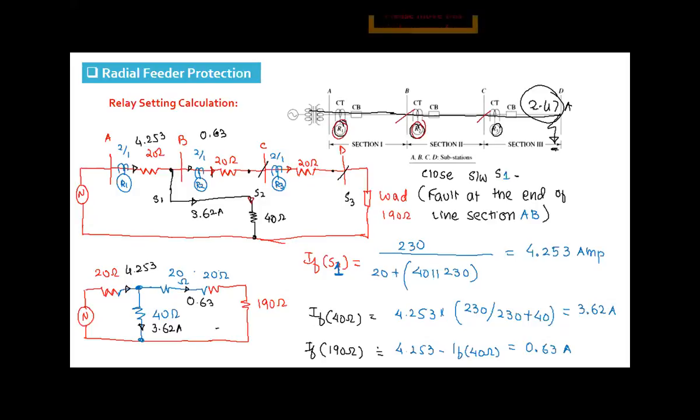R1: obviously 2 ampere is pickup and current is 4.25. Okay, so it is going to operate. Then who will provide backup to R1? Backup to R1 will be provided by the protection scheme at this substation. It may be a bus bar or any other generator or transformer, because now the line is over. It is the last line.